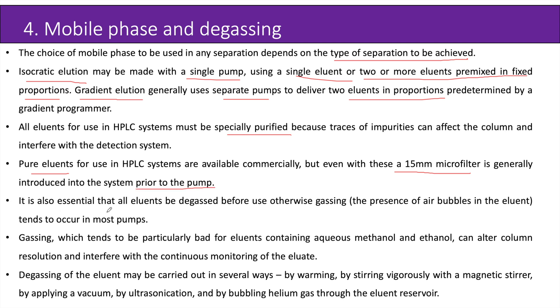It is also essential that all eluents be degassed before use; otherwise, gassing — the presence of air bubbles in the eluent — tends to occur in most pumps. Gassing, which is particularly bad for eluents containing aqueous methanol and ethanol, can alter column resolution and interfere with the continuous monitoring of the eluate. Eluate is the mobile phase containing the separated analyte molecules. Degassing of the eluent may be carried out by warming, by stirring vigorously with a magnetic stirrer, by applying a vacuum, by ultrasonication, or by bubbling helium gas through the eluent reservoir.